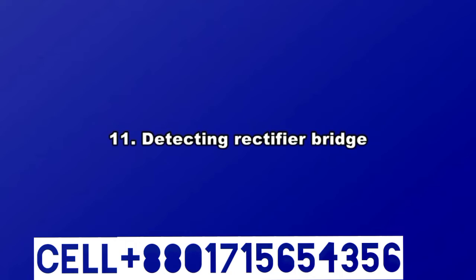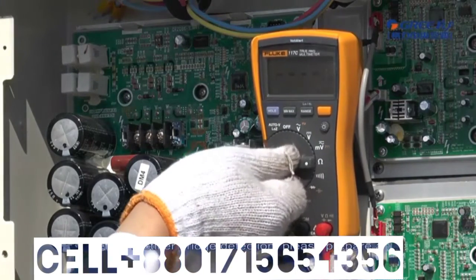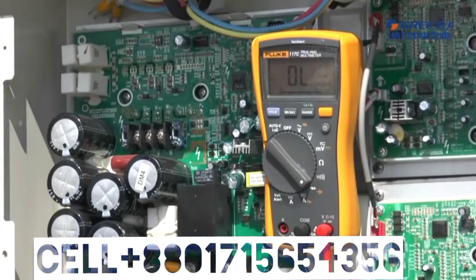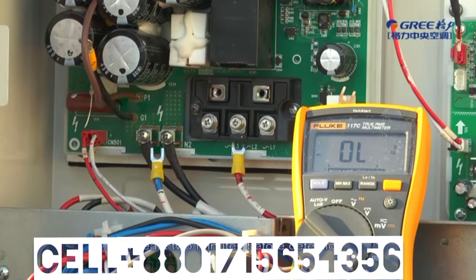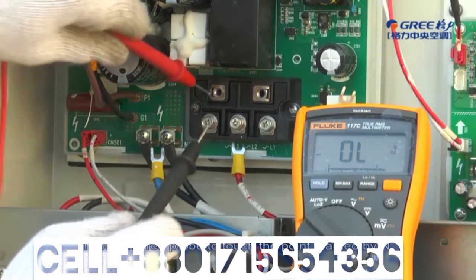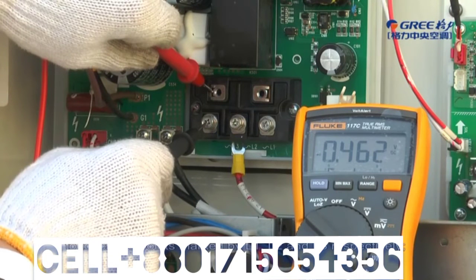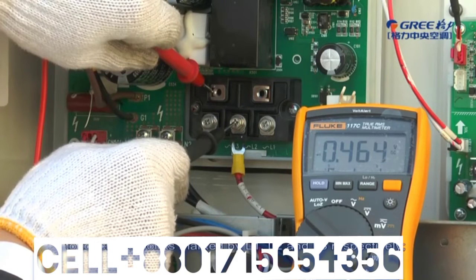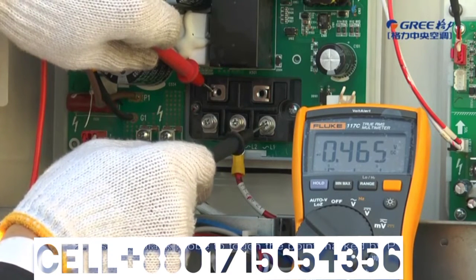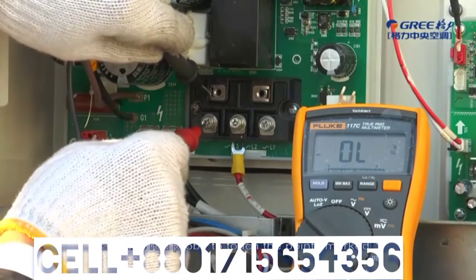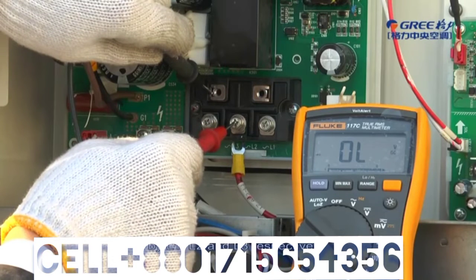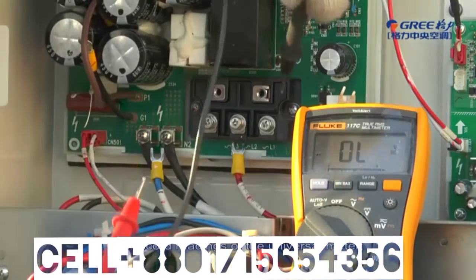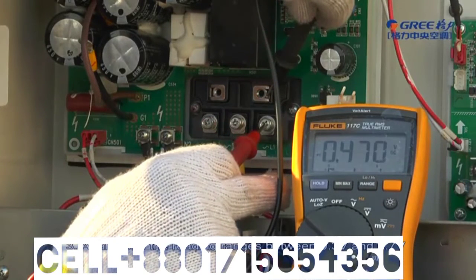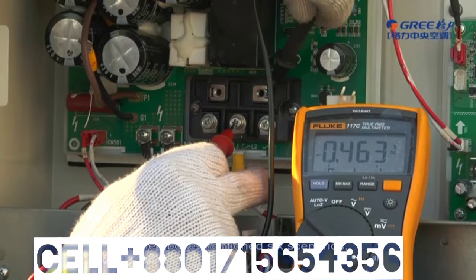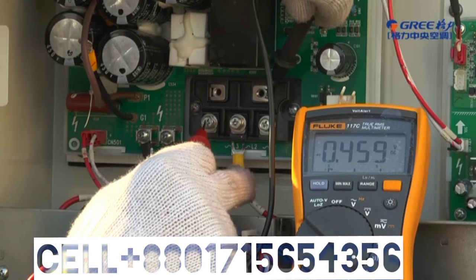11. Detecting rectifier bridge. Before rectifier bridge detection, please prepare a digital universal meter and switch it to the diode. Make sure the entire unit has been powered off for at least 2 minutes before detection. Detection method. First, use the red probe to touch the point marked by N and the black probe to touch the points marked by L1, L2, and L3 respectively. 2. Use the black probe to touch the point marked by P and the red probe to touch the points marked by L1, L2, and L3 respectively, and record readings of the universal meter. 3. Analysis. If the reading ranges between 0.3 volt and 0.7 volt in the above-mentioned 6 scenarios, the rectifier bridge is normal. If the reading is 0 in one or multiple scenarios, the rectifier bridge is damaged.